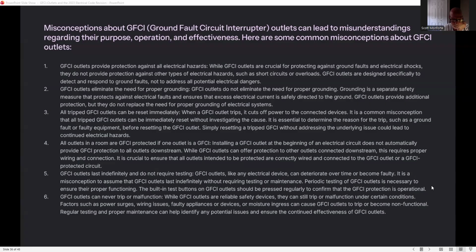All tripped GFCI outlets can be reset immediately. Well, when testing GFCI outlets, if it cuts out power to the connected devices, it is a common misconception that all GFCI outlets can be reset without investigating the cause. It's essential to determine the reason for the trip, such as a ground fault or faulty equipment, before resetting the GFCI outlet. Simply resetting a tripped GFCI without addressing the underlying issue could lead to continual electrical hazards.